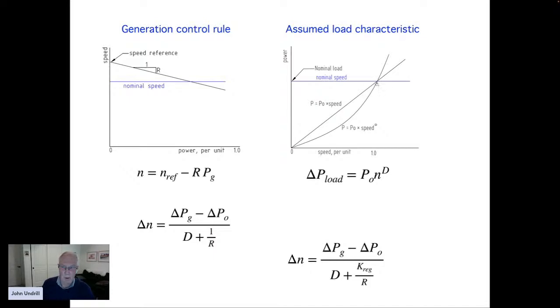Well, a lot of the load is pumps and fans, and we normally characterize the load on the power system by taking a linear approximation of the change in load with change in speed, and we use the index D. So we can say power increases as the Dth power of speed. Well, if I characterize the load on the system by that, and the production of power on the system by that, and I require that the generation equals the load, and I do some algebra, this and this combine to give me this. If I have a change in load, I have a change in generation and a change in speed, and the speed change will be related to the change in power by the regulation or droop factor R of the drooping governor relationship and the D factor that I use to characterize the load. This has been in use for 80 years.